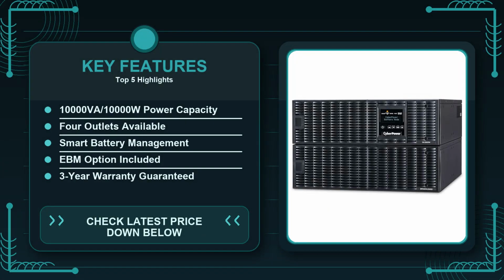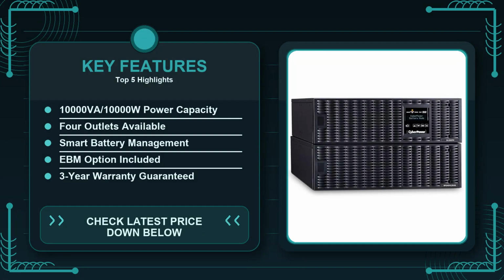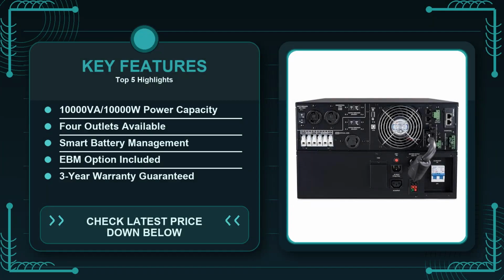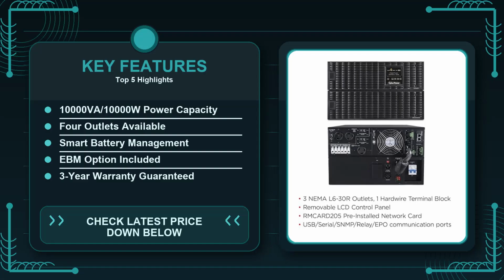On the flip side, because the UPS is always converting power, it runs a bit hotter than a line interactive model. In a tightly packed rack, you'll need to make sure there's enough airflow, or you'll see the internal temperature creep toward the upper 40s C under full load. It's not a deal breaker, but it's a hidden trade-off that some first-time buyers overlook.